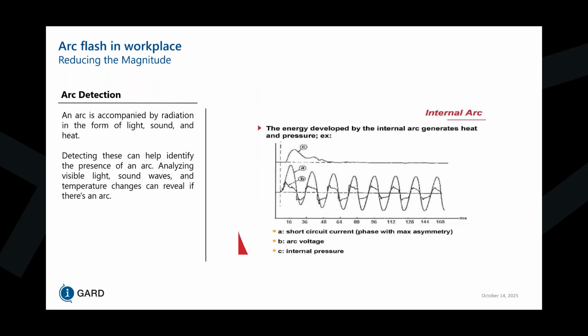And the energy developed by the internal arc generates heat and pressure based on the curves here. So we have short circuit current denoted as A, the arc voltage, which is going to be B, and then internal pressure, which has an impact directly off the bat and within the first cycle of this wave.